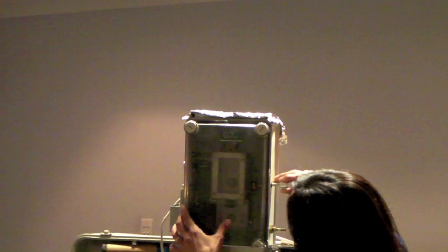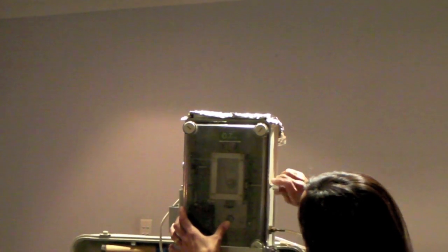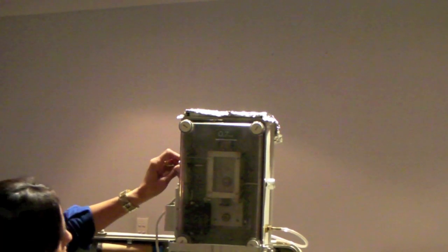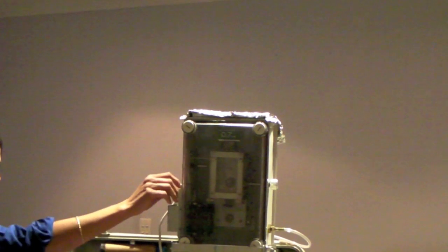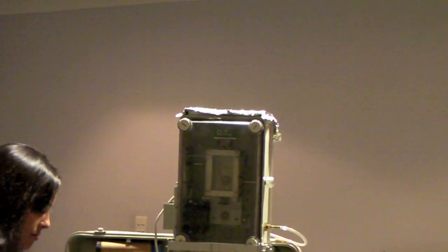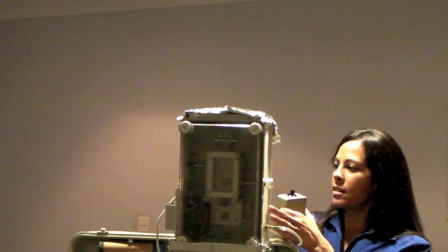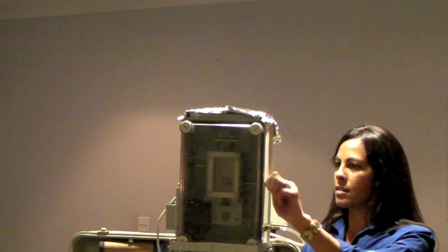In our demonstration, you can see a small box inside a larger box. This smaller box simulates our instrument enclosure. Once we have a sufficient fuel and oxygen mixture, we create a spark inside the instrument enclosure. You will notice combustion occurs only in the instrument enclosure, and the alfoil lid moves slightly. This proves a pressure wave reached the larger box from inside the smaller box via our flame path.